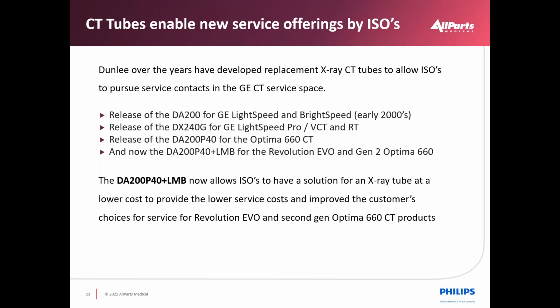So I've had the good fortune in my career to have worked with Dunlee on a number of different tube projects, even on the Lightspeed and Brightspeed tubes with the DA200 introduction in the early 2000s. And then later on, the release of the DX240G used on Lightspeed Pro, VCT, and RT systems. And then later on for the Optima 660 CT, where we have the DA200 P40. That's a ball bearing based tube. And then later on, GE moved into using a liquid bearing tube, LMB. And so Dunlee followed suit with developing that tube for the Revolution EVO and for the second version of the Optima 660, which shipped with liquid bearing tubes.